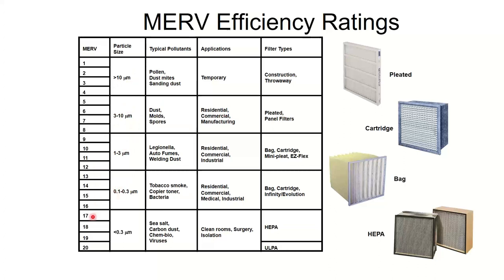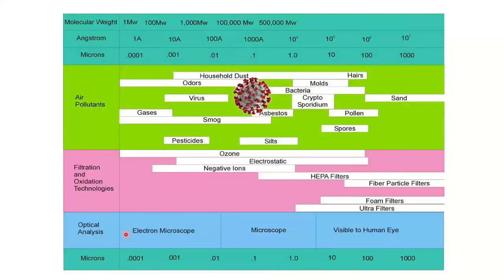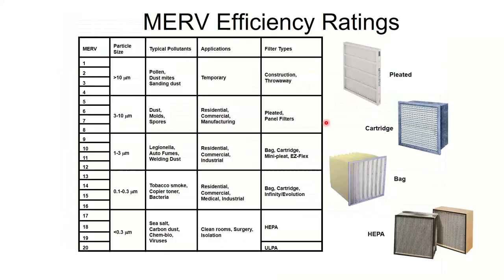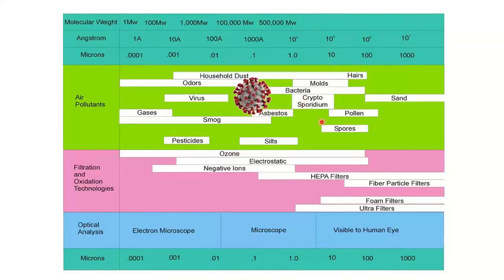As I move up the MERV scale, I can catch smaller and smaller things. How small? If I go back to my scale over here, if I had, say, a MERV 7 or 8, which is kind of like a low-end, rooftop-type filter, that's a micron 3 to 10 type range. So I'm catching stuff like this. Hair, pollen, sand, I'm catching with a MERV 8 filter. I'm not getting the little stuff, though.